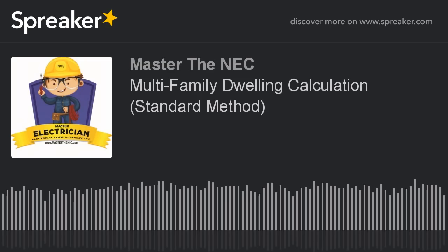You had the motor equation that I gave you was a 0.5 horsepower air handler, and it was a 120 volt air handler. Not sure why I did that, but I gave it to you at 120 volt. I showed you how to do the service and the neutral based on all those. I even showed you how to apply the general lighting demand values in Table 220.42 in order to be able to apply the lighting demand load. So really, that's everything that you need to do.